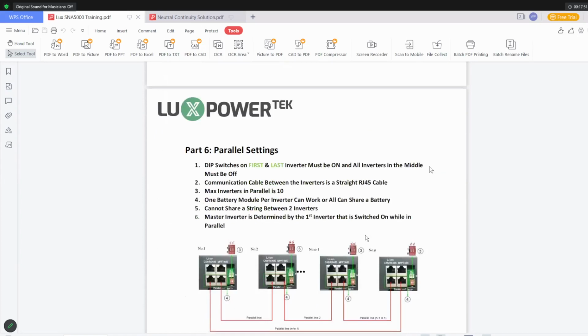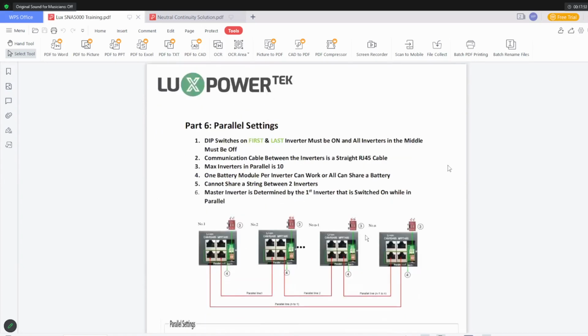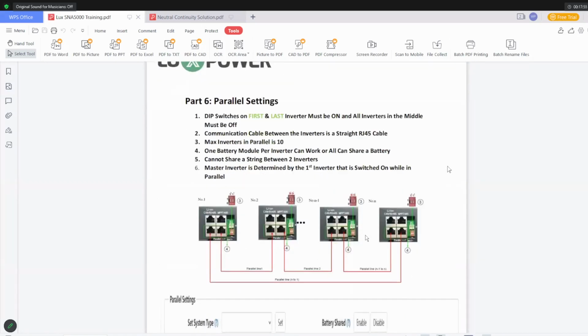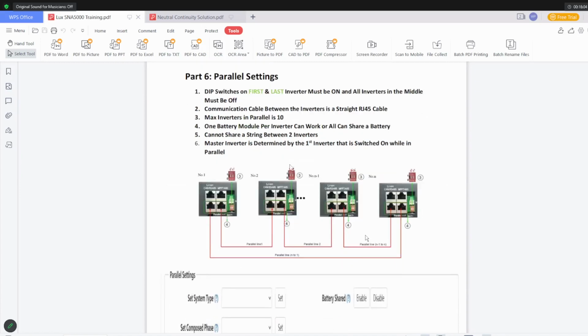Going down to the parallel settings: the SNA5000 can have up to 10 inverters in parallel, but 8 inverters is recommended. The diagram you'll follow is shown here. To explain how this works, if you have 4 Luxpower inverters in parallel, the first inverter and the last inverter must have their dips on.